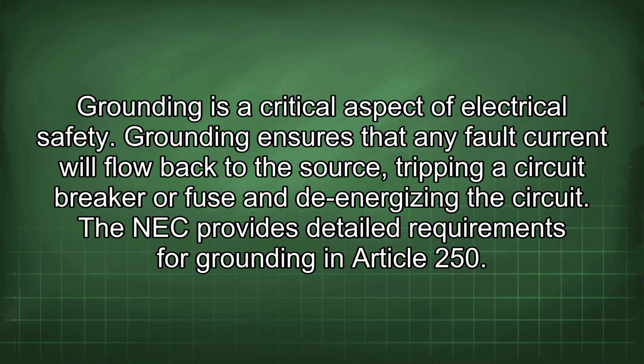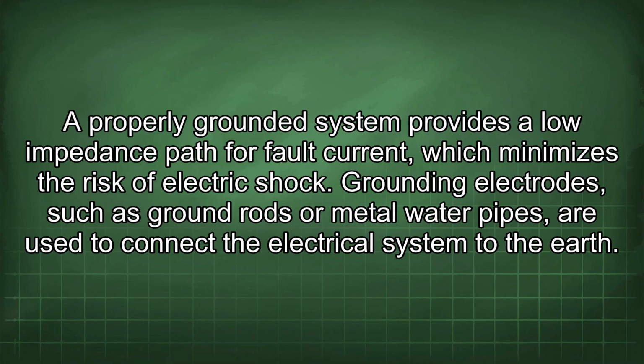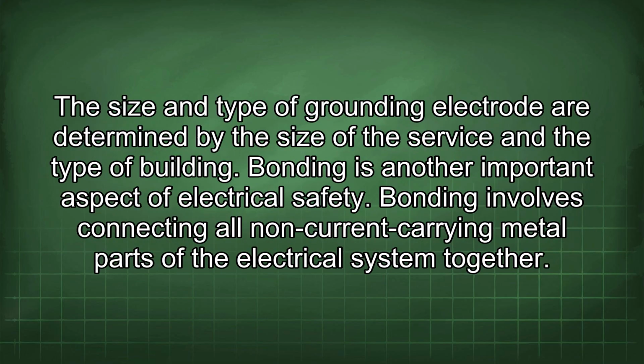Grounding is a critical aspect of electrical safety. Grounding ensures that any fault current will flow back to the source, tripping a circuit breaker or fuse and de-energizing the circuit. The NEC provides detailed requirements for grounding in Article 250. A properly grounded system provides a low impedance path for fault current, which minimizes the risk of electric shock. Grounding electrodes, such as ground rods or metal water pipes, are used to connect the electrical system to the earth. The size and type of grounding electrode are determined by the size of the service and the type of building.